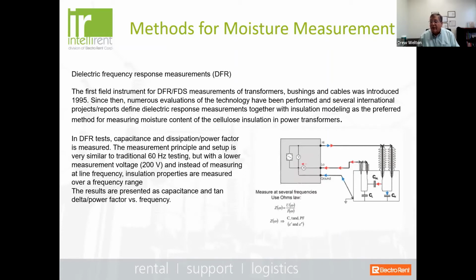And the first instrument for DFR was actually manufactured back in 1995, but since then, numerous evaluations of the technology have been performed at different international projects and reports to actually define the modeling that's built into this. So what is a DFR test? Well, that's a capacitance and dissipation power factor measurement at a very wide frequency range. And this is a low voltage, very non-invasive test.